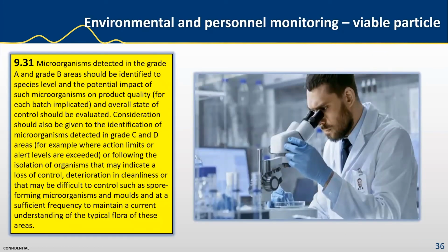Finally, under the environmental and personnel monitoring under viable particle, microorganisms detected in the grade A and B areas should be identified to species level and the potential impact of such microorganisms on product quality for each batch implicated. An overall state of control should be evaluated. Consideration should also be given to the identification of microorganisms detected in grade C and D areas, for example, where action limits or alert levels are exceeded, or following the isolation of organisms that may indicate a loss of control, deterioration in cleanliness, or that may be difficult to control, such as spore-forming microorganisms and molds, and at a sufficient frequency to maintain a current understanding of the typical flora of these areas.